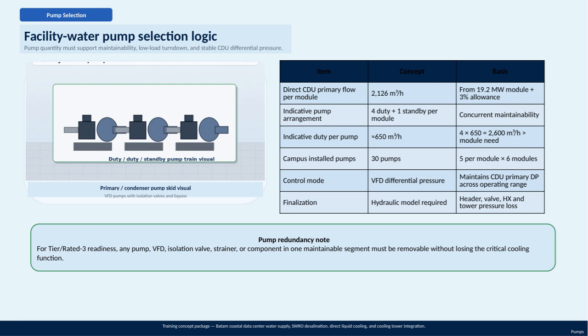From the table, you can see the core design parameters. Each module requires about 2,126 cubic meters per hour of direct CDU primary flow, based on a 19.2 megawatts module plus a 3% margin. To achieve this, we plan an arrangement of 4 duty pumps plus 1 standby per module, ensuring concurrent maintainability. Each pump handles roughly 650 cubic meters per hour, collectively exceeding the module's required flow to provide a safety buffer.